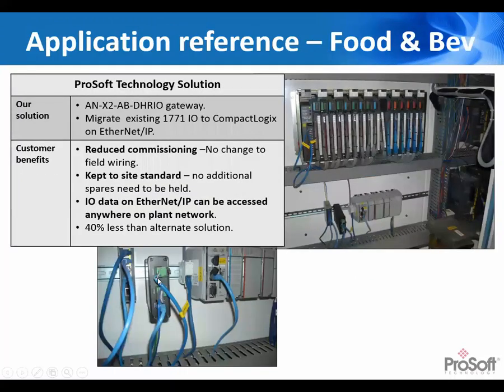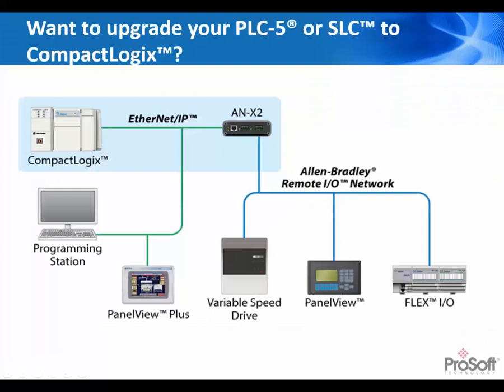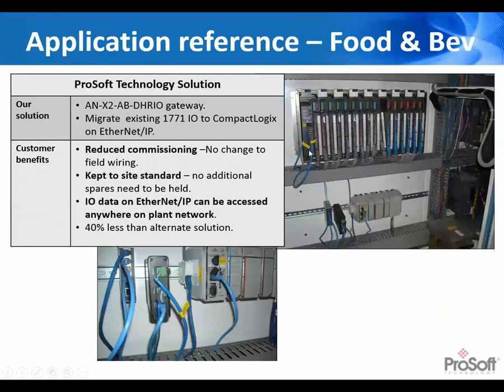Question: do you need to take out the processor of an old rack to hook up the I/O? If you're controlling the remote I/O rack in this sort of structure, yes, I believe you do. I think you need an ASB module to do this, which is what they did in Wales - they had an ASB module to keep the existing rack here to hook up the I/O. Hopefully that answers your question.